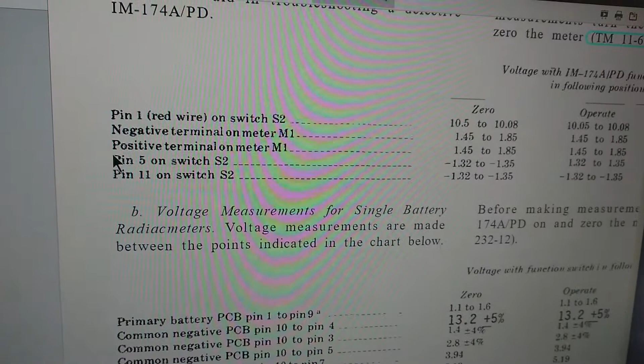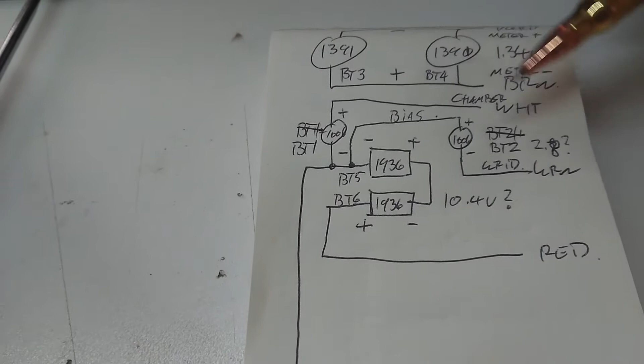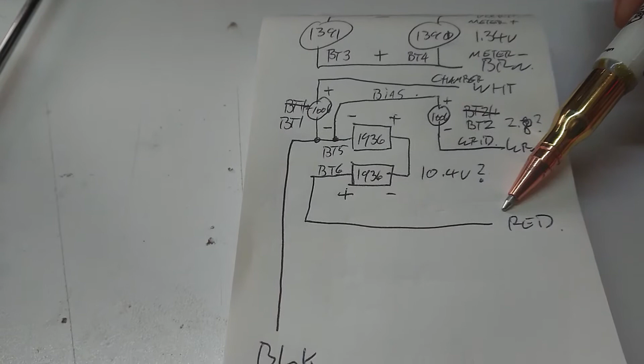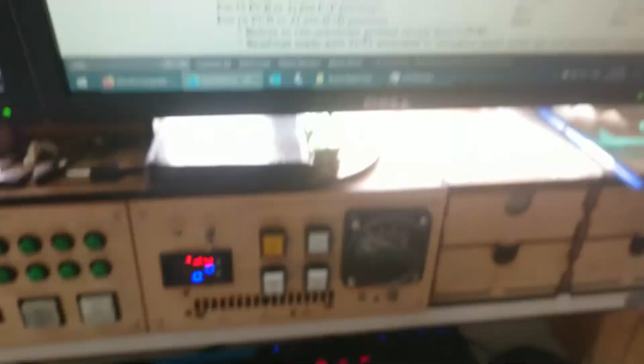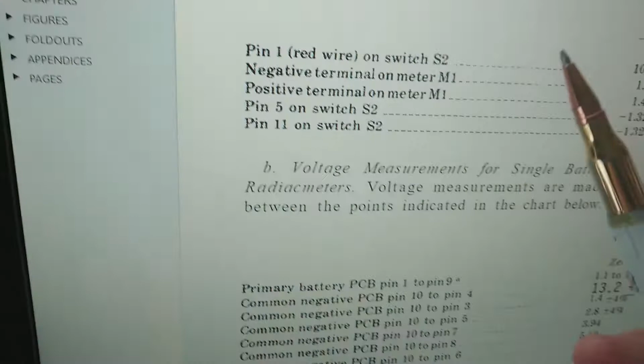Alright, so further to my research here, I have found the testing procedure where you check the voltages. And they reckon pin 1 on the red wire on switch S2 should be at 10.5 volts. Now, if we go back to my diagrams, which I am slowly updating here, with, of course, the battery numbers. The red wire here goes back to these series connected batteries here, which should total about 10.4 volts or thereabouts, which we'd expect to see on the red wire. So that is adding up. These are about 5 volt batteries or somewhere about that. So that gives me a good idea that I'm on the right track. It also means that the negative and the positive terminals on the meter should be about between 1.45 and 1.85 volts. And we can see here that that's pretty well in keeping with the voltage we would expect to see there.